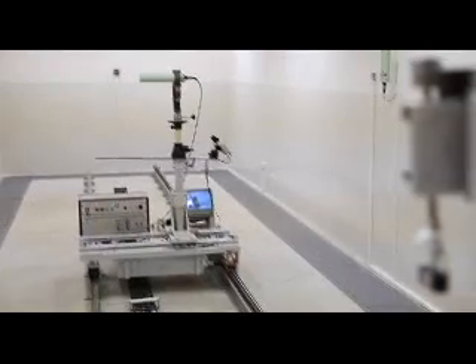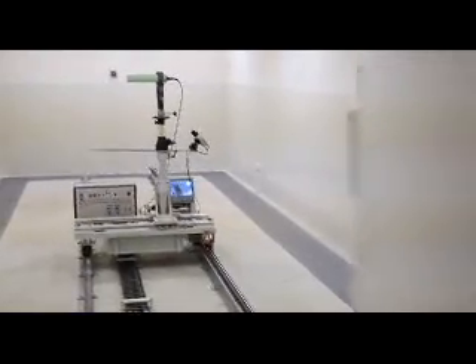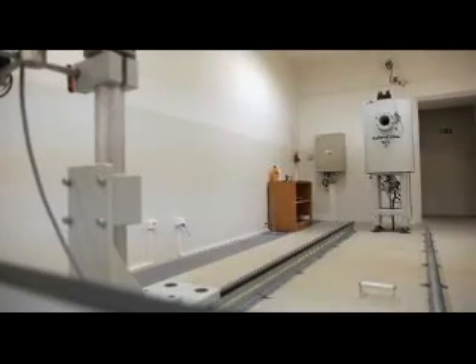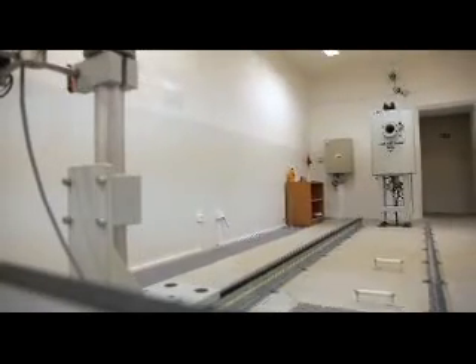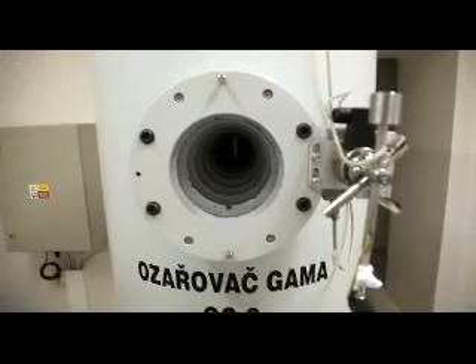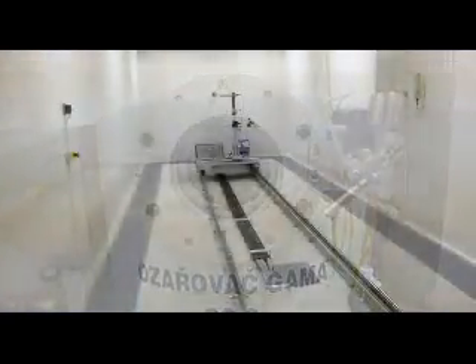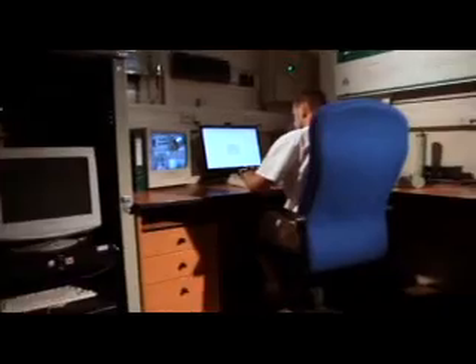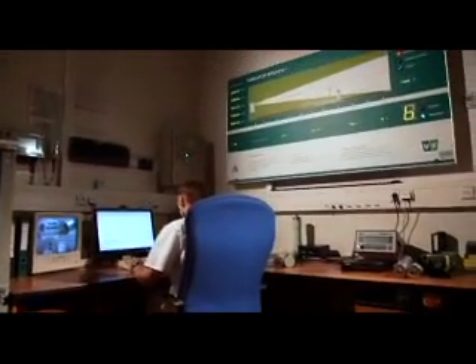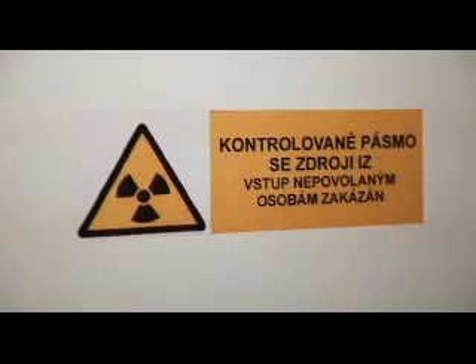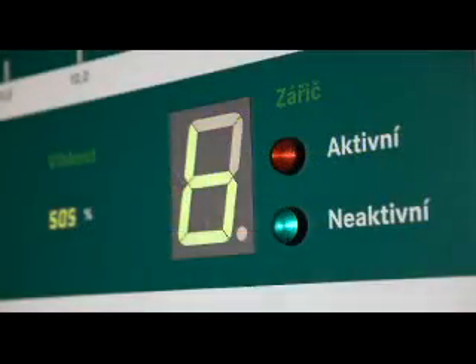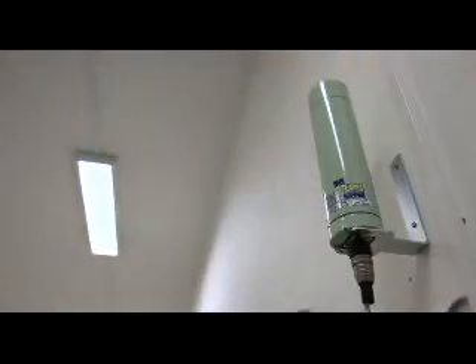Health and safety is of the highest priority when operating the ionizing radiation calibration laboratory. The laboratories designed and provided by us are equipped with every essential safety feature, such as emergency shutdown buttons, safety measures during power loss, door lock to irradiation room and open door indicator, motion sensors in the link corridor between control room and calibration room, visual and audible warning before source exposure. The laboratory is also equipped with a radiation monitoring system.